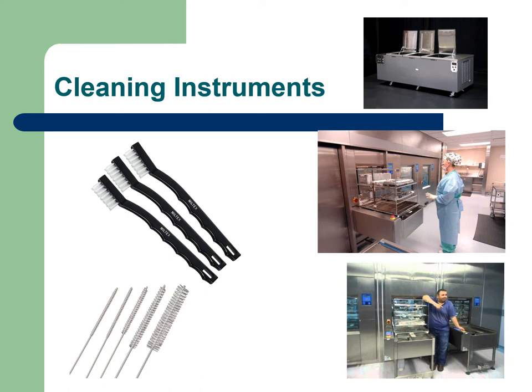So instruments might go right into the ultrasonic. When I was at the VA here in Phoenix, everything that could got hand cleaned if it was grossly contaminated, then everything went into the ultrasonic, and after that we put the instruments into what we call the washer sterilizer. Now the washer sterilizer does not actually sterilize - it's like your dishwasher at home, except it probably gets a little hotter. The washer sterilizer serves as the dishwasher, if you will.